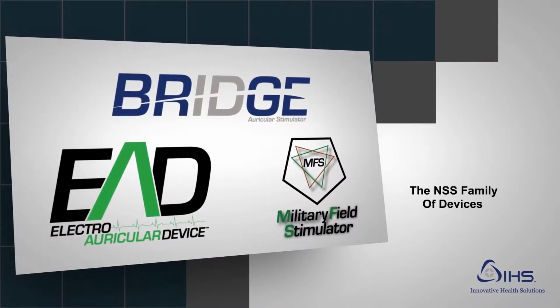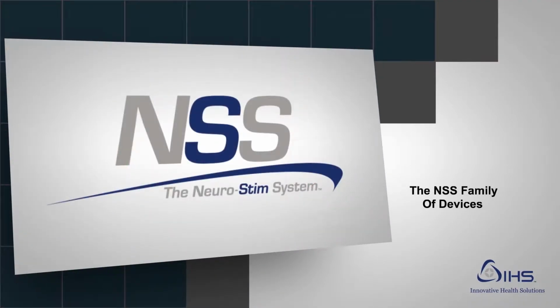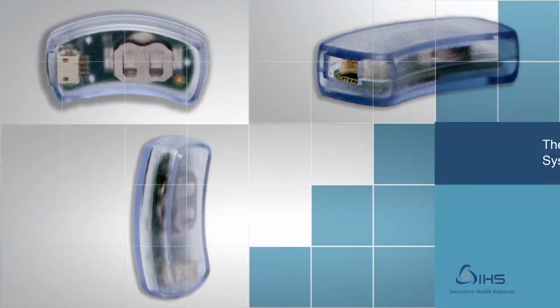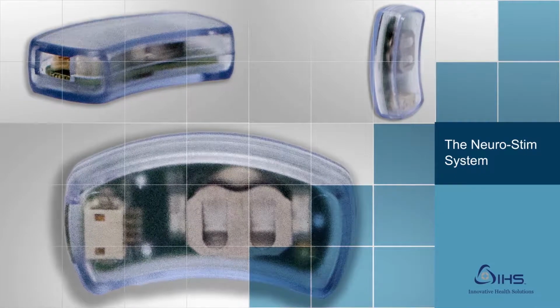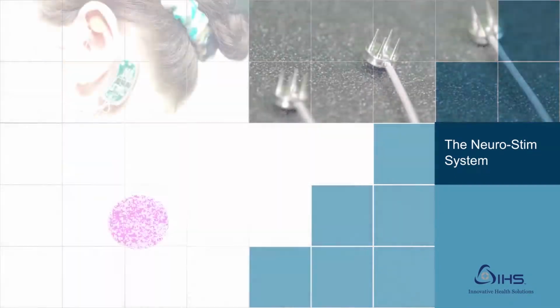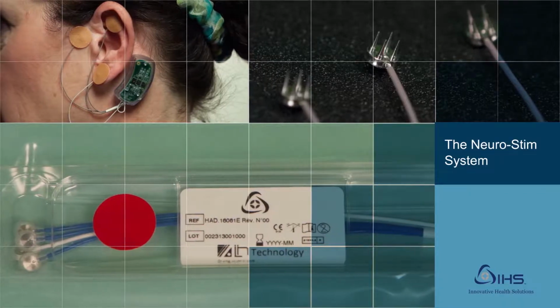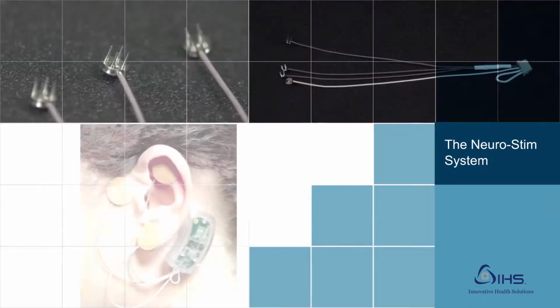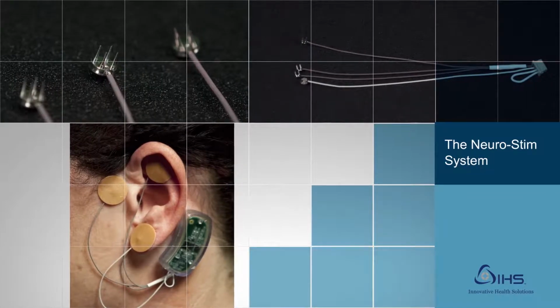For this report of findings, the EAD, MFS, and Bridge, although packaged separately, are collectively referred to as the NSS, or Neurostim System. The NSS is a group of neurostimulation medical devices consisting of a battery-operated solid-state generator externally affixed by double-sided tape to the skin beside the ear, 4 wire connecting leads, and 4 attached electrode needle arrays, each consisting of 4 1.5 mm needles designed to be percutaneously implanted into the dermis of the external ear.